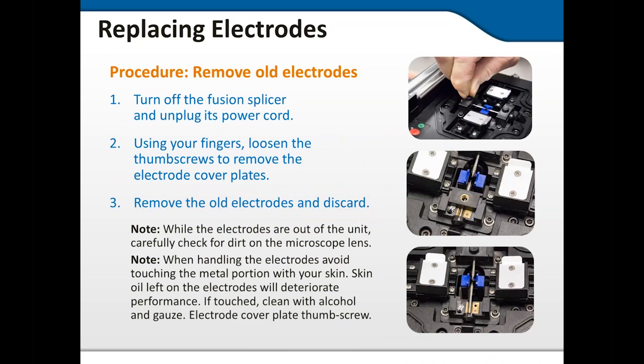Removing old electrodes. Very important. Turn off the fusion splicer and unplug the power cord. Using your fingers, loosen the thumb screw to remove the electrode cover plates. Remove the old electrodes and discard. Note, while the electrodes are out of the unit, carefully check for dirt on the microscope lenses. Then handle the electrodes. Avoid touching the metal portion with your skin. Your skin has oil, and that will affect the electrodes. If touched, clean the electrodes with alcohol and gauze.